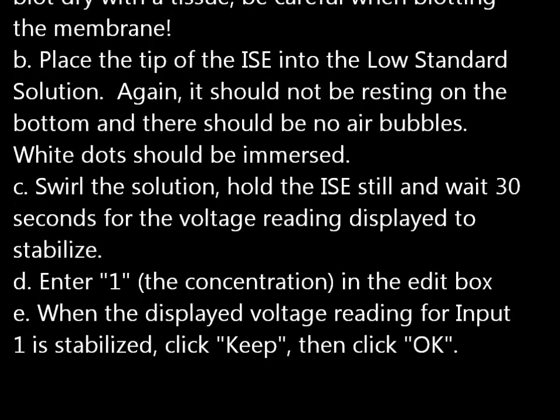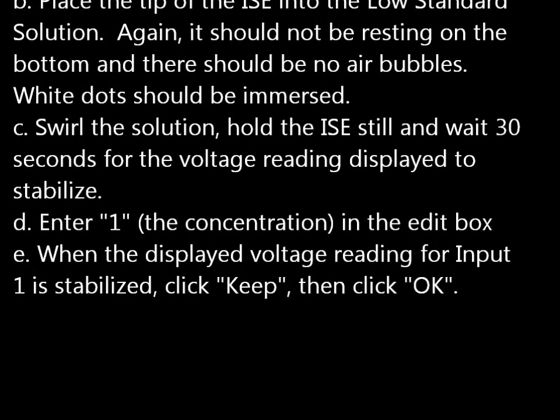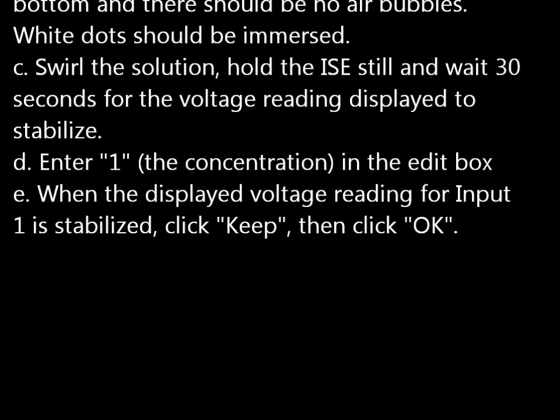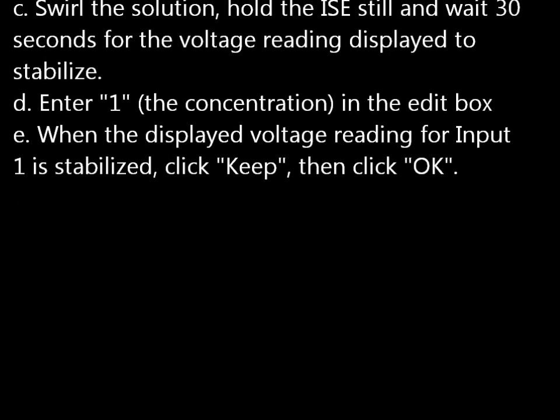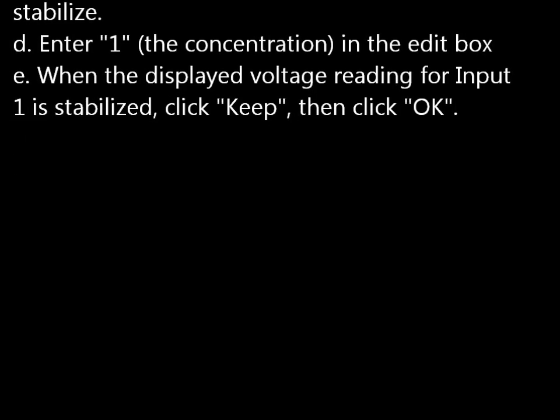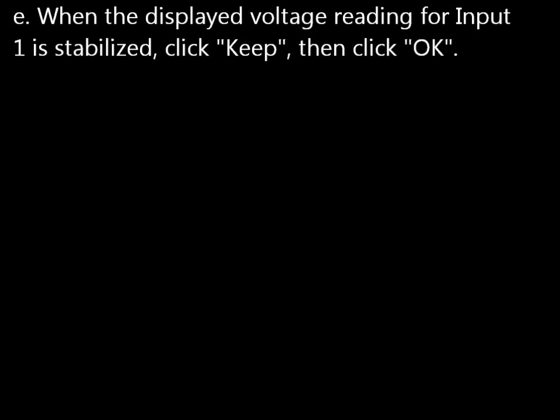Swirl the solution, hold the ISE still, and wait 30 seconds for the displayed voltage reading to stabilize. Enter 1, the concentration, in the edit box. When the displayed voltage reading for input 1 is stabilized, click Keep and then click OK.